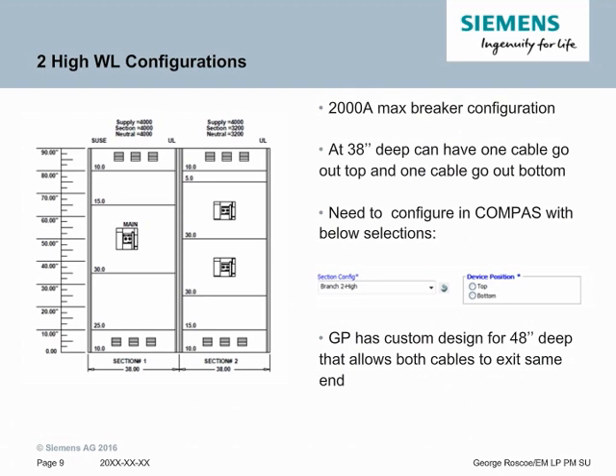On this slide, it illustrates how to select the 2-high WL configuration option. It is under section configuration of branch breakers. You select branch 2 high, and then right next to it will appear the device position, which, as mentioned previously, one needs to be on the top and one needs to be on the bottom to lay out appropriately.